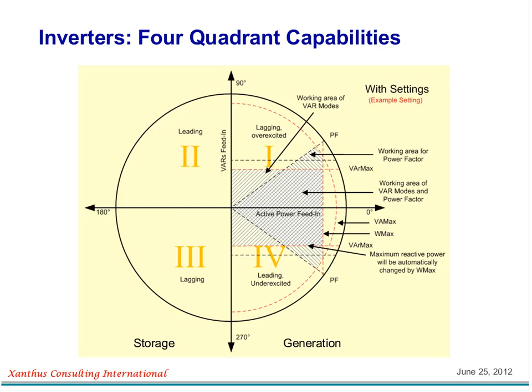So let's take a look at some of the modes, functions that have now been defined through both an EPRI project and through the IEC work, where we have arrays of volt-VAR settings. If you see the graph at the bottom, VARs generated on the vertical axis and system voltage on the horizontal, you can create an array that matches this function, so that if the system voltage gets too high, you change the VARs generated—you decrease them, and vice versa.